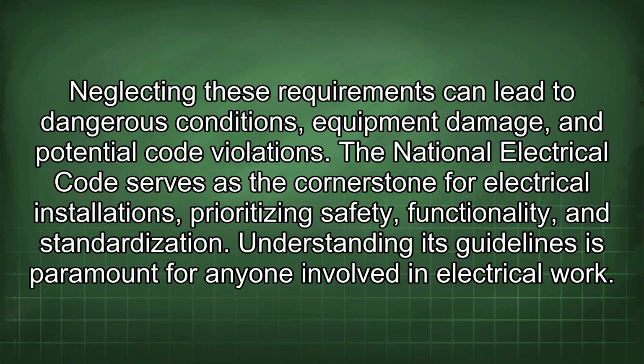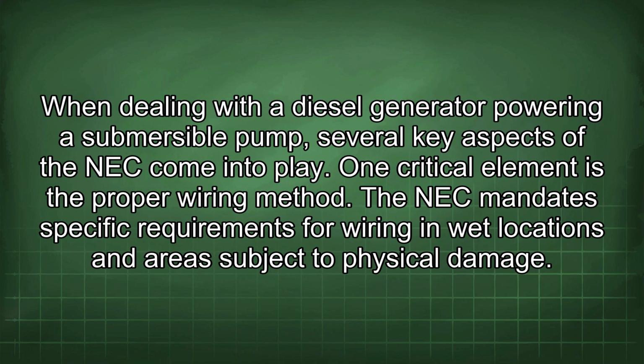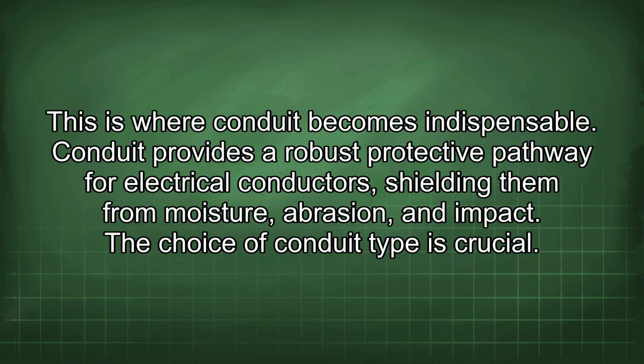The National Electrical Code serves as the cornerstone for electrical installations, prioritizing safety, functionality, and standardization. Understanding its guidelines is paramount for anyone involved in electrical work. When dealing with a diesel generator powering a submersible pump, several key aspects of the NEC come into play. One critical element is the proper wiring method. The NEC mandates specific requirements for wiring in wet locations and areas subject to physical damage. This is where conduit becomes indispensable.